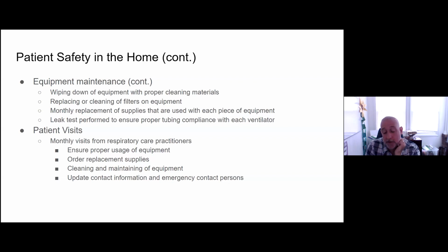So a lot of our air inflow filters can be taken out, kind of washed in the sink a little bit, and then put back in. There are particulate filters which do need to be switched out on a regular basis, whether it's once a month or once every 3 months, whatever the manufacturer protocol is. So those you don't want to put water on, you just want to throw them out and put a new one on.